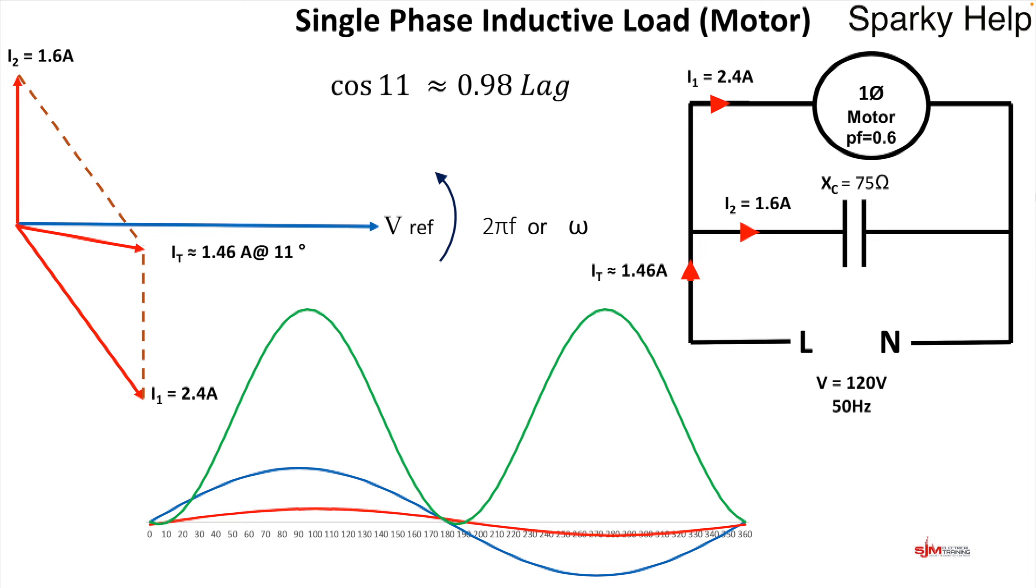Now what impact does this have on. Well basically it means. The IT part. Which would be the supply going to your circuit. Can be much smaller. Which means the cable is smaller. Which means the circuit breaker is smaller. Which means the demand on the system is smaller. But more importantly. From a commercial or industrial point of view. Who pay for VA. They save money on their energy.